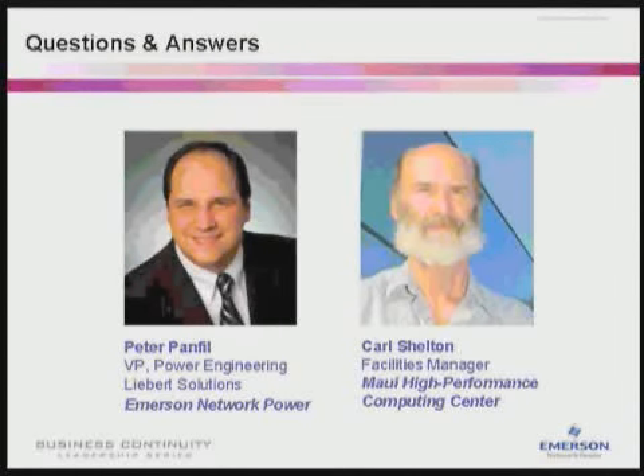All right. Next question from Michael at a power company in Nevada. What's the most common business continuity mistake you see in data centers? And what's the most common outside threat? Peter? Well, I would have to say that a fairly common blind spot we see is failing to adequately anticipate your future growth. It's not so much that you don't know what's going to happen in the future. It is that applications come up that you hadn't put into your existing planning that you have to deal with on an on-the-spot basis. It's tempting to size your UPS and cooling system to an initial load and then add modules as the load increases or the applications increase in their heat density. But this has the potential for reduced reliability and increasing your costs in the future. We advocate sizing the initial UPS module no less than about a third of the projected load. That gives you some built-in expandability without compromising any reliability.